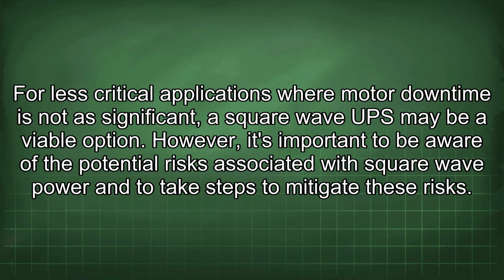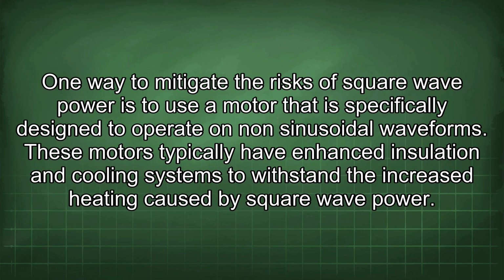For less critical applications where motor downtime is not as significant, a square wave UPS may be a viable option. However, it's important to be aware of the potential risks associated with square wave power and to take steps to mitigate these risks. One way to mitigate the risks of square wave power is to use a motor that is specifically designed to operate on non-sinusoidal waveforms. These motors typically have enhanced insulation and cooling systems to withstand the increased heating caused by square wave power.